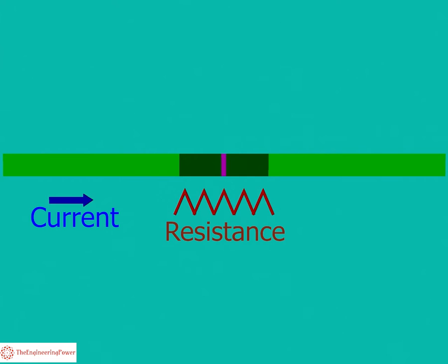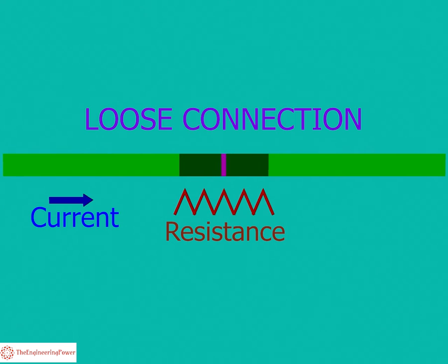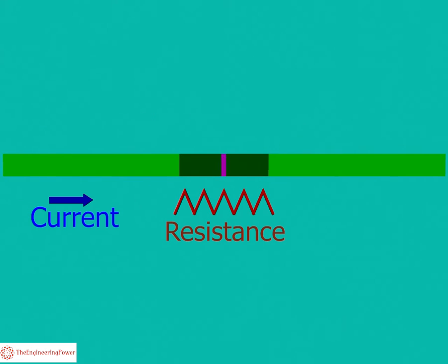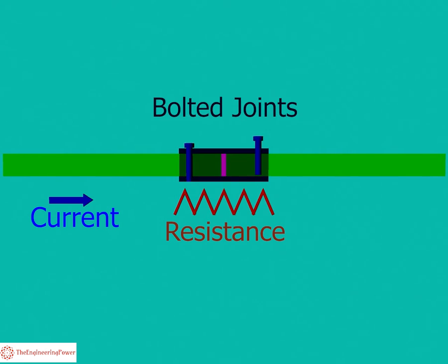The purpose of contact resistance test is to measure the resistance of electrical connections like joints, terminations, connectors, etc. The aim of this test is to verify that the connections are properly made and there is no loose connection. It also detects inadequate tension on bolted joints and contamination on corroded contacts.